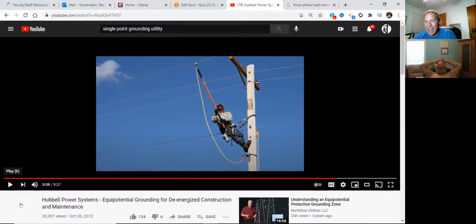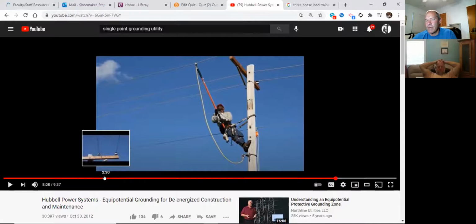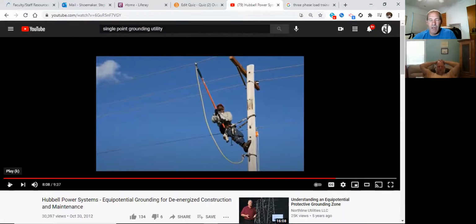3. 3, okay. He's not going to the neutral with it here. So I think, in our safety department, that's why we were instructed to go to every structure and do the 3-point grounding like you saw in the beginning, or the 4-point actually, or 5-point: ground rod, neutral, and all 3 phases. So you had insurance that if you had induced voltage on the line, you were working inside the zone at a grounded point. Does that make sense to everybody? Say yeah. Yes. Okay. Thank you for that.